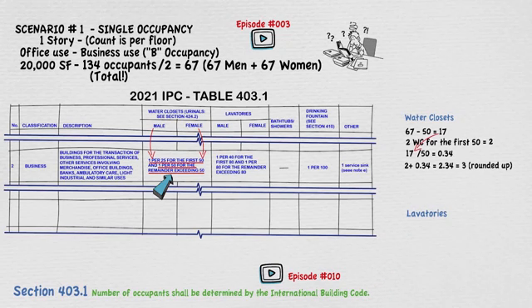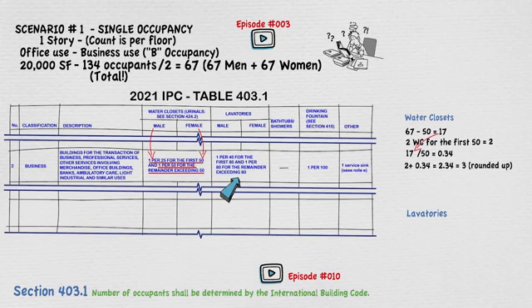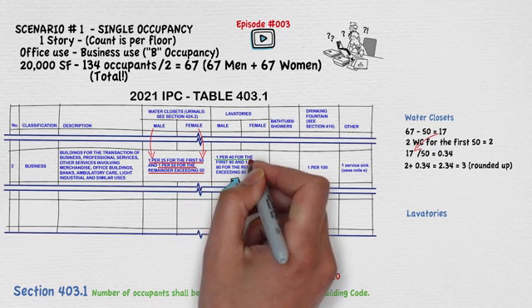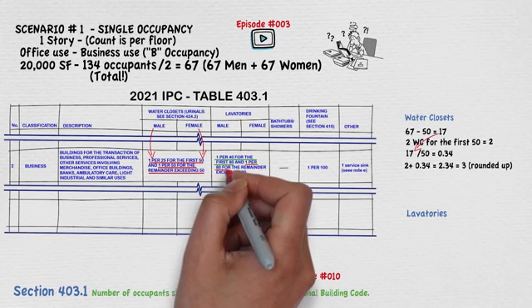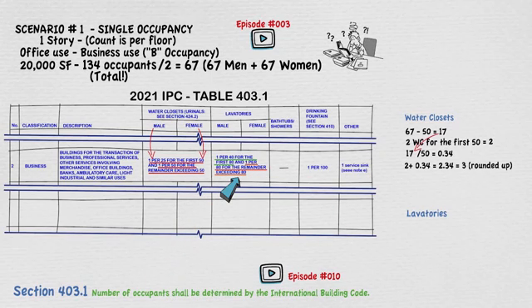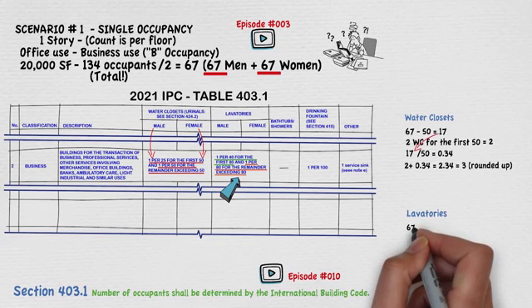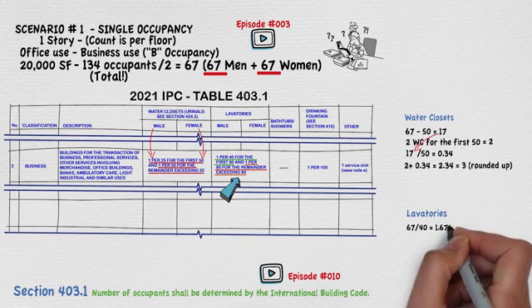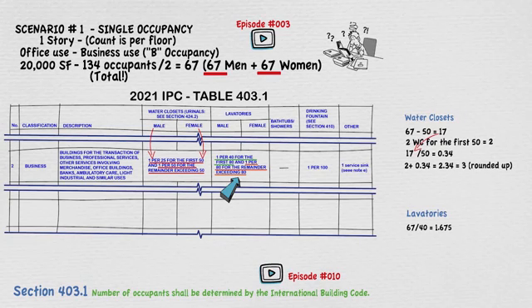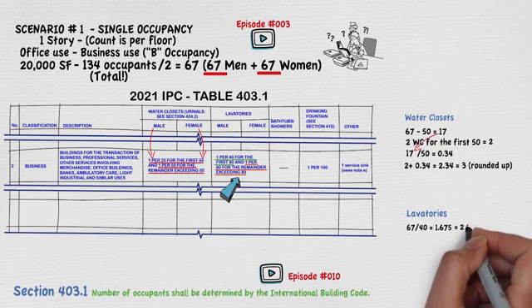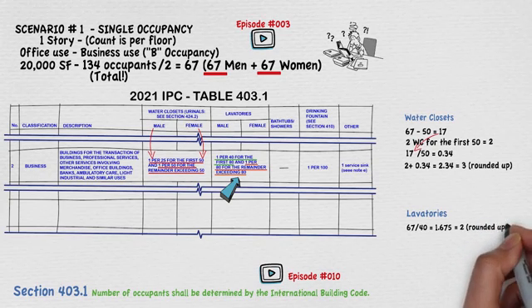We now repeat this mathematical process for the lavatories using the information on the chart. Like the water closets, the requirement for male and female are the same: 1 lavatory per 40 occupants for the first 80, and 1 per 80 for the remainder exceeding 80. However, our occupant load is only 67, so it does not exceed 80. Since we have 67 occupants divided by 40, we need 1.675 lavatories — rounded up, 2 lavatories are required.